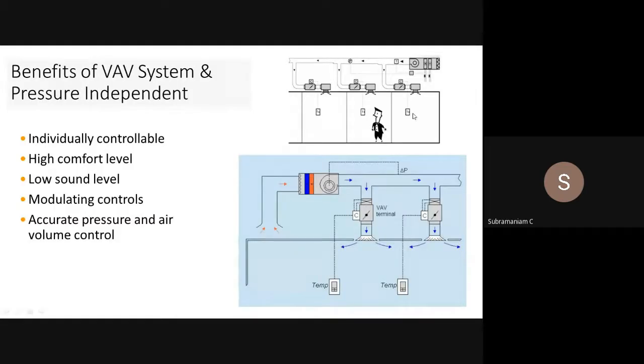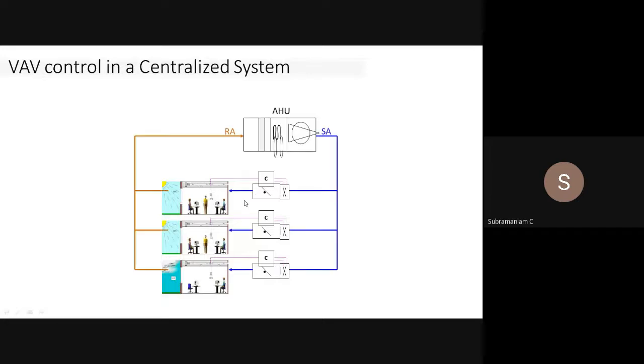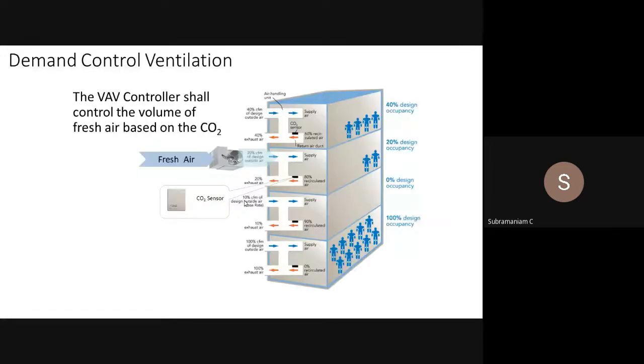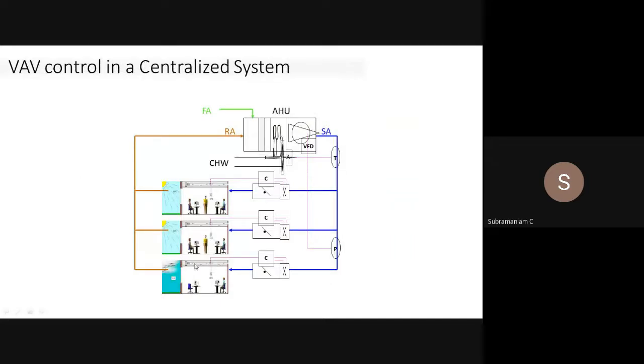For example, there are 3 cabins. You have your VAV. You can put your temperature sensor, and then accordingly the damper. There is a controller on the VAV box. It is going to take care of that position. So, for example, you are having a small VAV in a centralized location here. So this is what is going to happen. You are having the AHU supplying air to all the VAV boxes, and then each VAV has got its own temperature control.